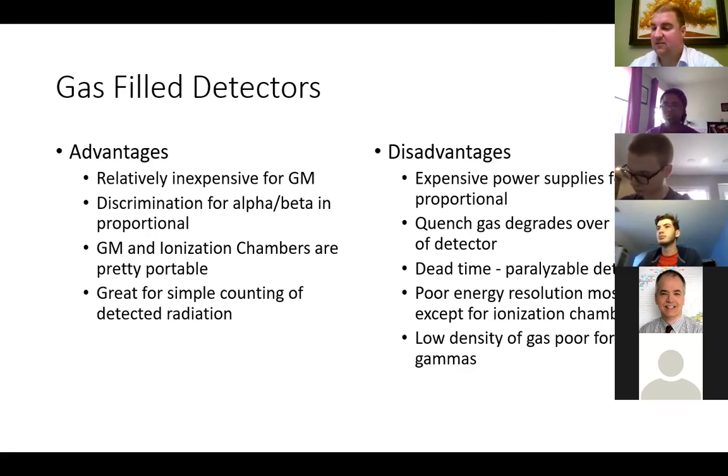Disadvantages of gas-filled detectors are that you have to have expensive power supplies for the proportional counters. The quench gas degrades over the lifetime of the detector. The gas-filled detectors have dead time. Many of them are known pretty much as being paralyzable detectors. So if you paralyze something, what does that mean?